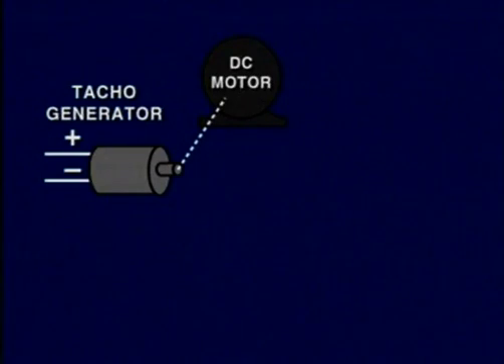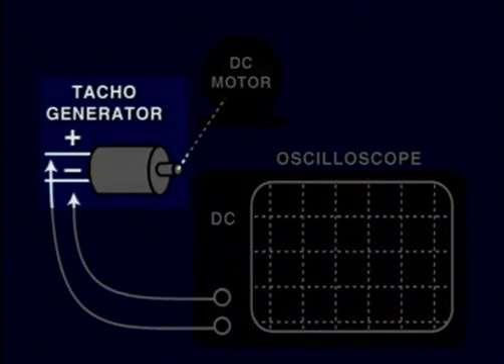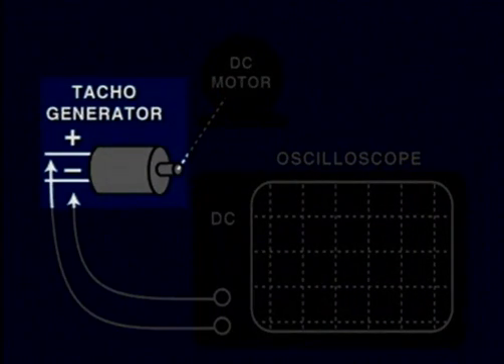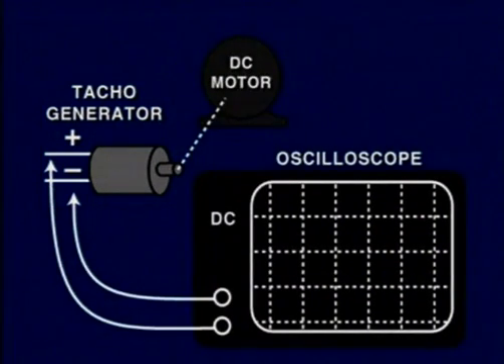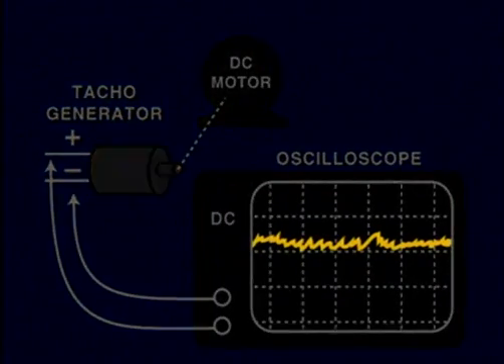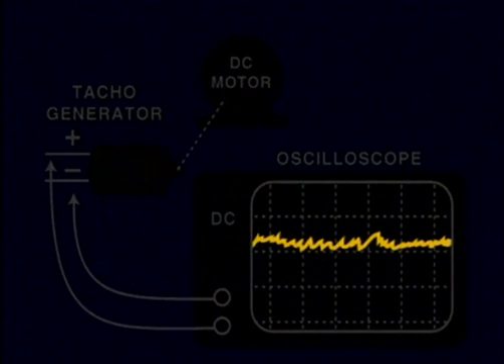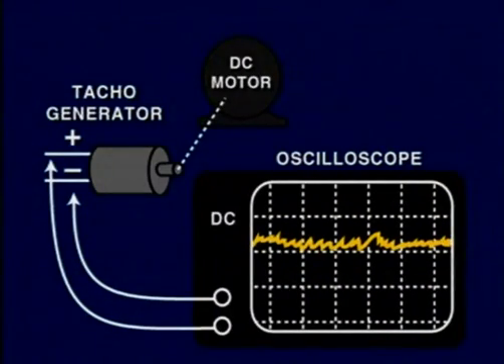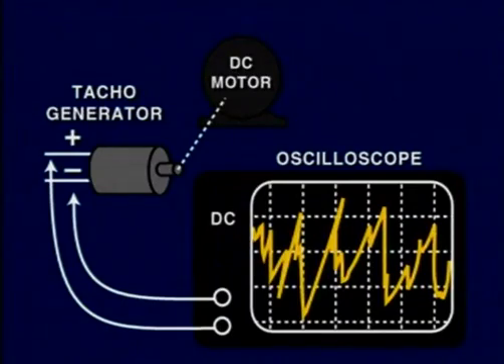Another signal that is good to check and make sure is present is the feedback, in this example from the tachogenerator. This tachogenerator provides a DC voltage proportional to the motor RPMs for use by the drive. In the scope, you should see a smooth DC signal providing feedback to the electronic control board, and that there are not large spikes in the system induced by electrical noise.